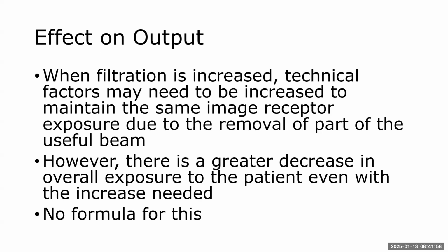So the bottom line is, even though you might have to add a little bit of mAs, the overall protection of the patient is so improved with filtration that it's worth it. Because if you leave those very low energy photons in the beam, what are they going to do? Just get absorbed right in the patient's skin, and that adds to their skin dose.